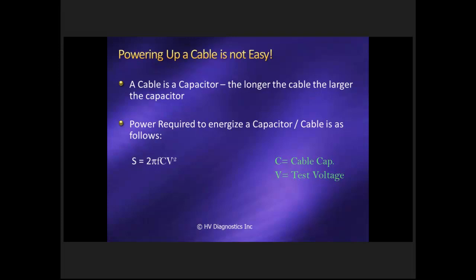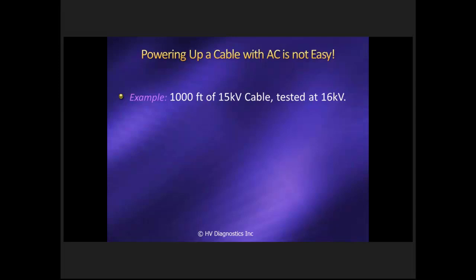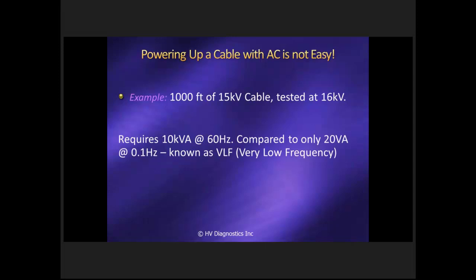Now why is this important? As an example, if you take a 1,000 foot run of 15 kV cable and test it at 16 kV, which happens to be the IEEE test voltage for 15 kV cable maintenance, you will require a 10 kilowatt power supply at 60 hertz. Even if you use resonant techniques, it's still a substantial amount of power. If you make that cable longer, or test it at higher voltages, the power requirement becomes even more severe, causing severe limitations, not only on the practical aspects of testing, but also on the length of cable you're able to test. At 0.1 hertz, based on that formula, you need 600 times less energy. At 0.1 hertz, you can energize with a 20 VA power supply. You can almost get that out of your car battery through a simple inverter.